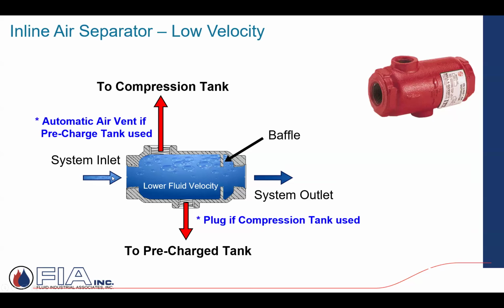and it gives the air bubbles that have been released from the heat source, that heat exchanger, that boiler or boiler plant, the chance to separate. So it's a very simple device, but it does work. It's more common residentially than commercial, but just be aware of this technology. Velocity is the method they use to separate the air from the water.